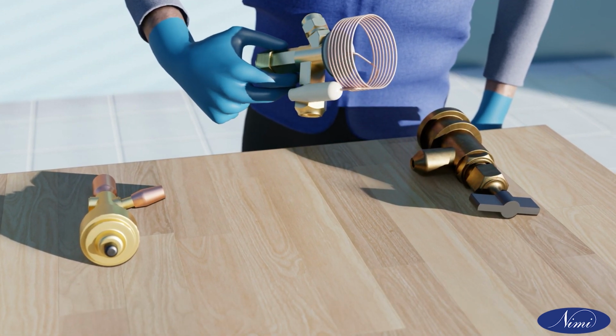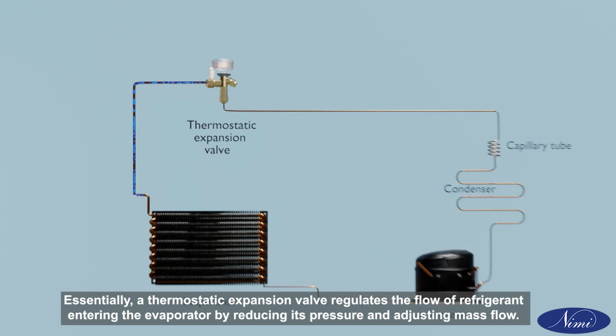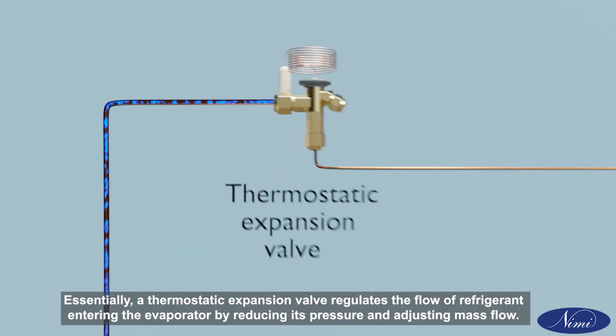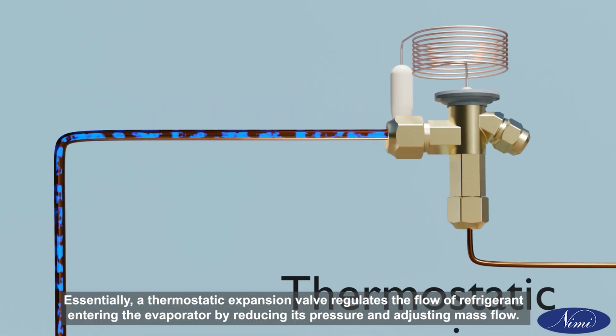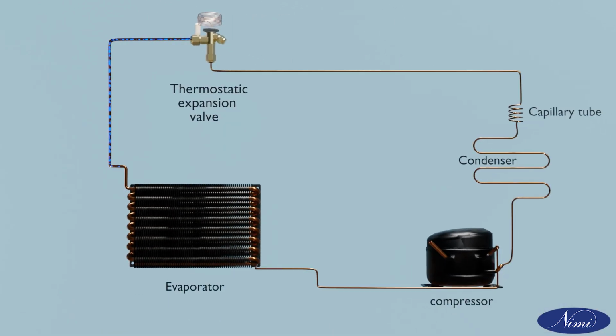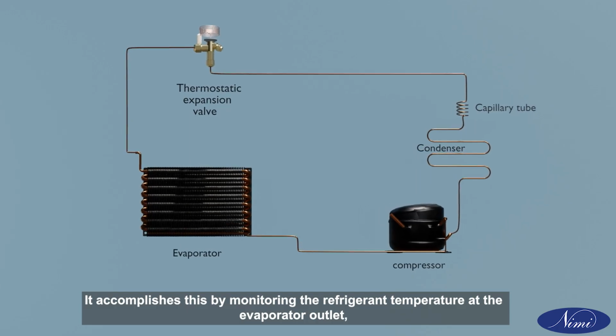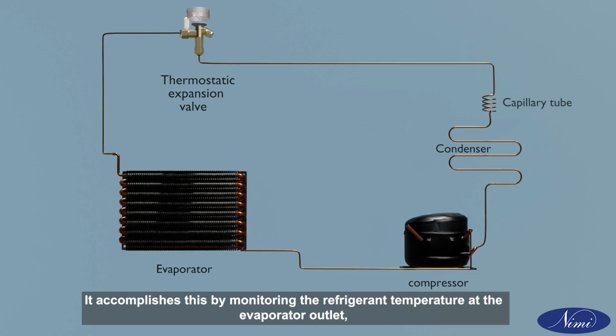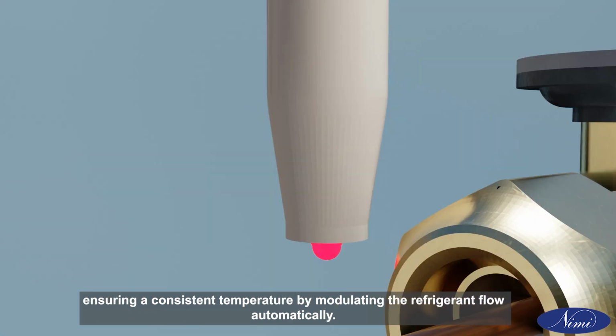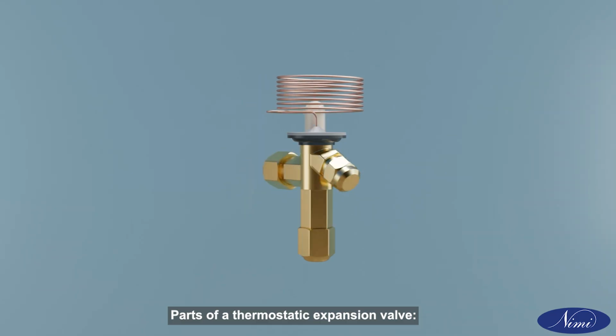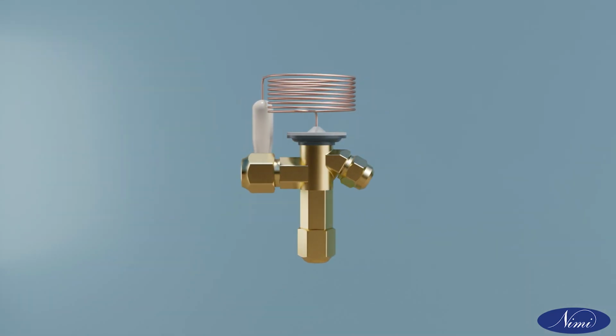Essentially, a thermostatic expansion valve regulates the flow of refrigerant entering the evaporator by reducing its pressure and adjusting mass flow. It accomplishes this by monitoring the refrigerant temperature at the evaporator outlet, ensuring a consistent temperature by modulating the refrigerant flow automatically. Parts of a thermostatic expansion valve.